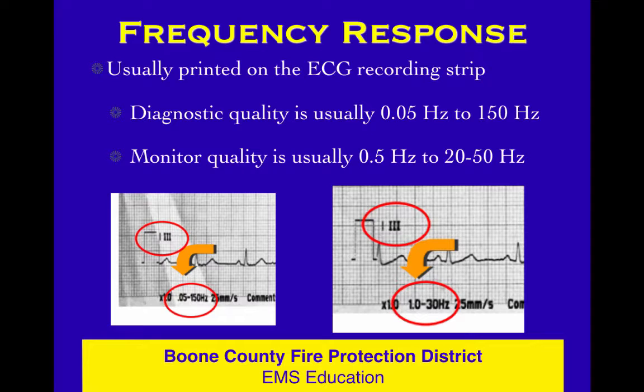You may have a monitor that has diagnostic quality capability on your limb leads. How would you know? You would look at the bottom of the strip and see the frequency response printed there. Diagnostic quality is going to have a decimal point and a zero — it's going to be .0-something — whereas monitoring quality is not going to have a zero; it's going to be .5 or something like that. You can see very clearly in those examples where it's printed for you.